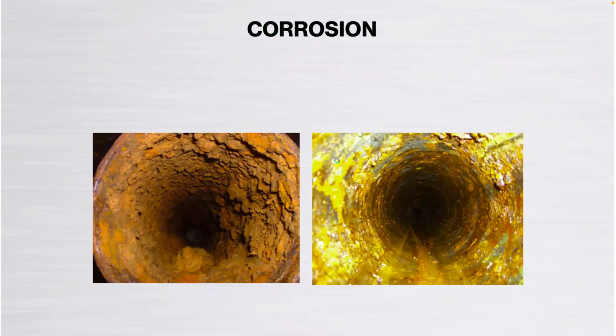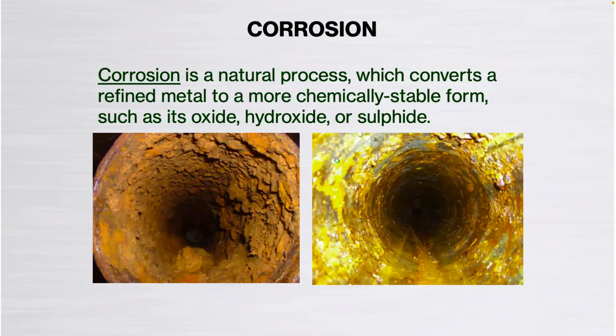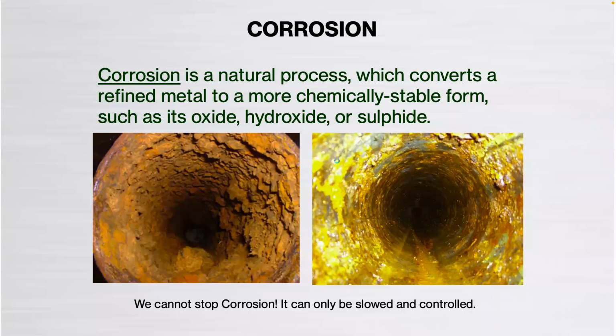So I covered off scale, really, and then talked about what makes water more corrosive. So let's talk about corrosion. There are actually different types of corrosion that we need to be aware of. But first and foremost, we can't stop corrosion. That's just not correct. It wouldn't be a technically correct statement. We can only slow it, or we can only control it. And that's really what we're going to cover off as we go through this.